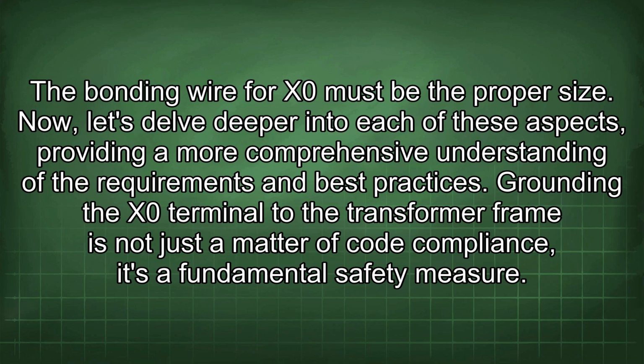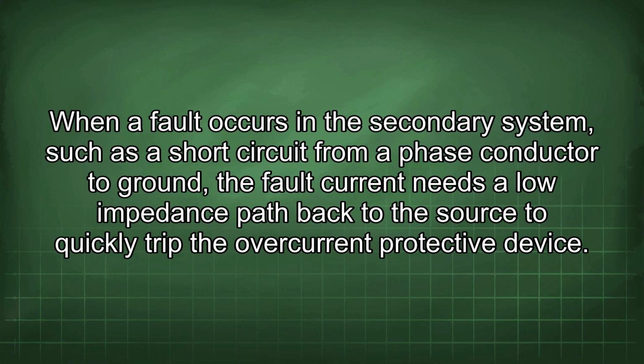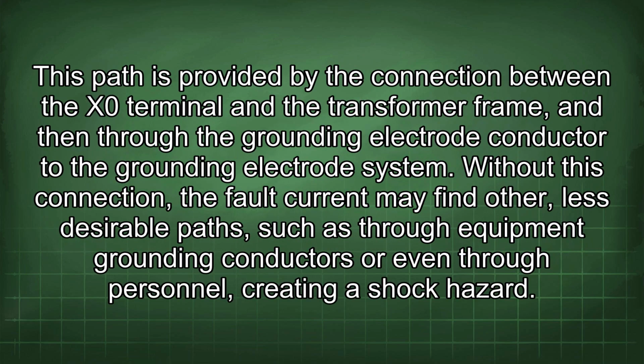Grounding the X0 terminal to the transformer frame is not just a matter of code compliance, it's a fundamental safety measure. When a fault occurs in the secondary system, such as a short circuit from a phase conductor to ground, the fault current needs a low impedance path back to the source to quickly trip the overcurrent protective device. This path is provided by the connection between the X0 terminal and the transformer frame, and then through the grounding electrode conductor to the grounding electrode system. Without this connection, the fault current may find other, less desirable paths, such as through equipment grounding conductors or even through personnel, creating a shock hazard.